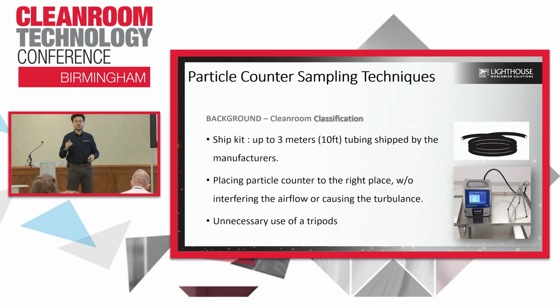This isokinetic probe design generally takes this magical number, 0.45 meter per second, which means if you have 0.45 meter per second flow at the height of the sample, then this diameter cuts a whole column of air, which will be enough to sustain 28.3 liter per minute sampling. So if it is, let's say, 100 liter, you'll be seeing a larger diameter so that this column will be enough to maintain 100 liter per minute, so that the air will be cut like a slice and there will be no turbulence. But what if you have, let's say, 0.30 meter per second, as in biosafety cabinet conditions? In this case, you'll be making it super isokinetic conditions, so that your system will work like a vacuum cleaner. That's why we have to take a look at the system design twice when we are selecting isokinetic sampling.